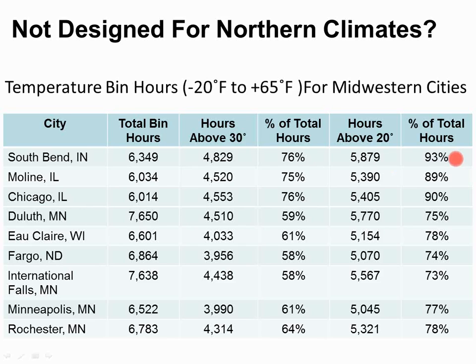Above 20 degrees is when heat pumps can do their thing, right? And depending on the heat pump you have, maybe you use the 30-degree number, and fine, only 76% of them, I can handle it. But the variable speed heat pumps, we typically can run them to colder temperatures and get capacity. So for right now's discussion, whether you're in Chicago at 90%, South Bend at 93%, somebody was from Minnesota on here, I think. You're at 77, which is still pretty good, right? There's a lot of hours that I can operate in a quote-unquote mild outdoor air temperature where heat pumps can really kind of shine.